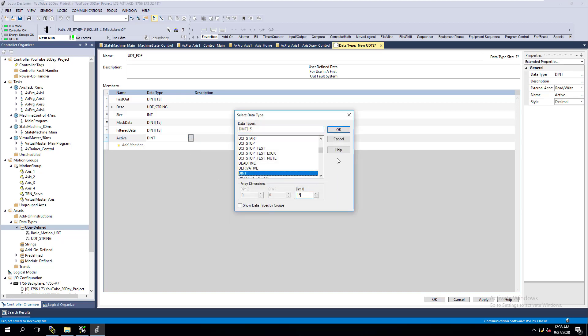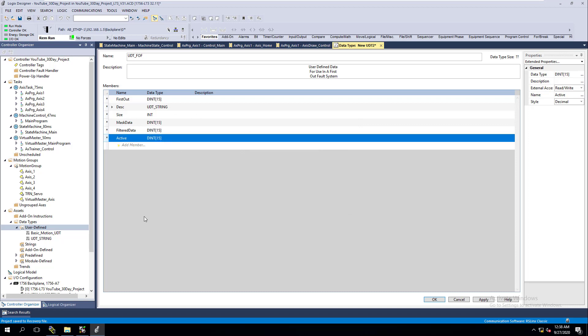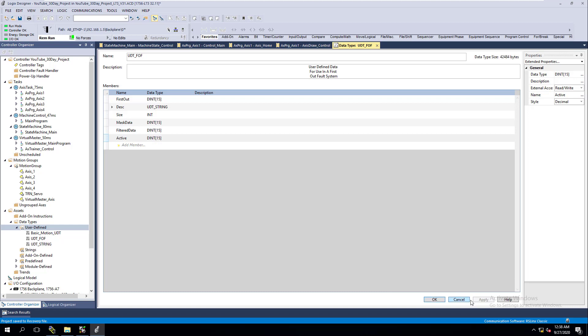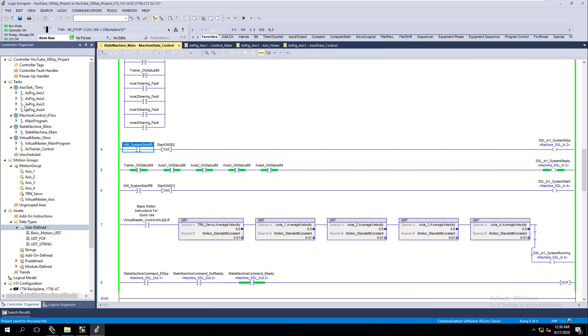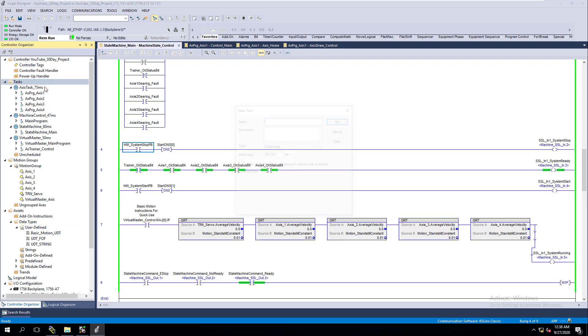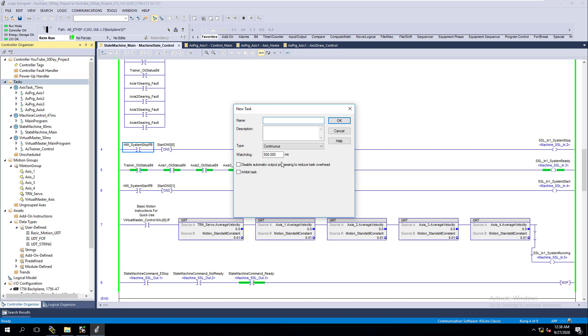Now we're going to actually use these. We're going to save and apply this. Then we're going to come in and make a new fault routine. We'll add another task and call it 'fault handling.' This is going to be periodic — I time everything properly. One of my tasks is 75ms, the next is 47ms, then 80ms, and this one we'll put at 125ms because faults don't necessarily need to run as frequently.